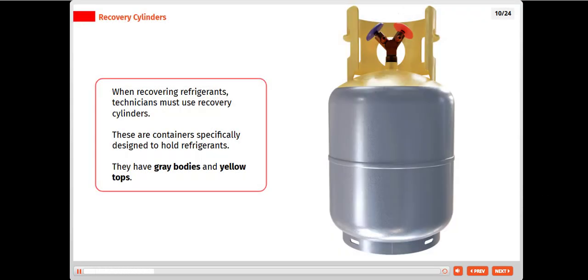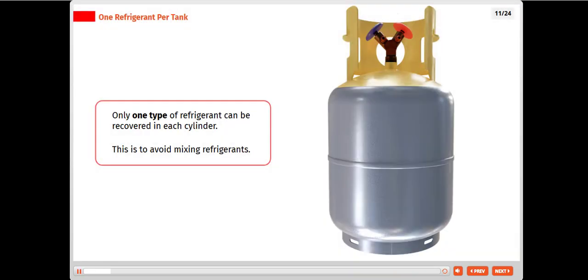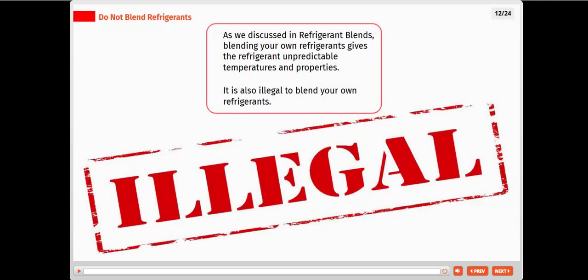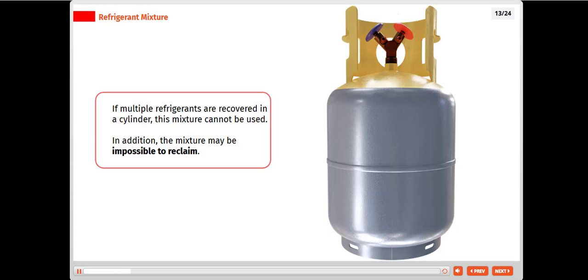When recovering refrigerants, technicians must use recovery cylinders. These are containers specifically designed to hold refrigerants. They have gray bodies and yellow tops. Only one type of refrigerant can be recovered in each cylinder. This is to avoid mixing refrigerants. As we discussed in refrigerant blends, blending your own refrigerants gives the refrigerant unpredictable temperatures and properties. It is also illegal to blend your own refrigerants. If multiple refrigerants are recovered in a cylinder, this mixture cannot be used. In addition, the mixture may be impossible to reclaim.